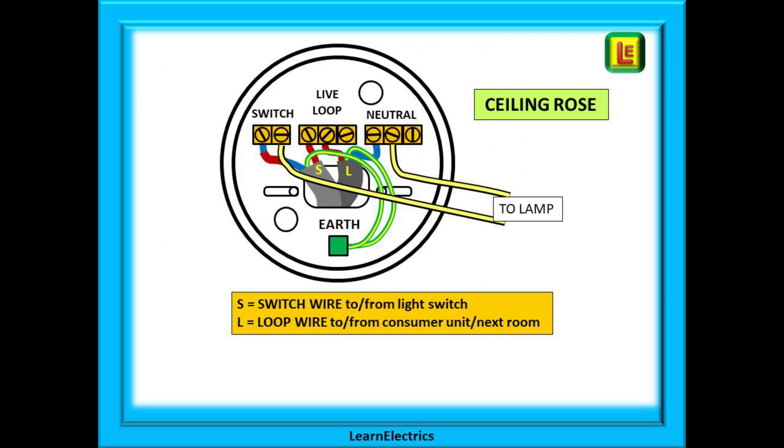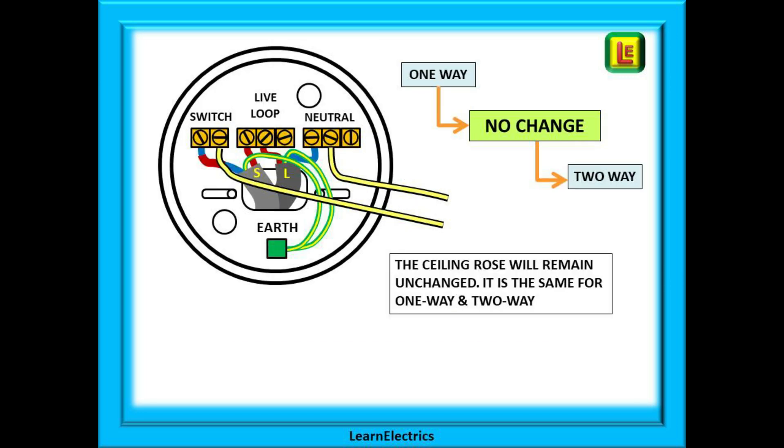We will use a standard three plate ceiling rose in this example and how to wire this up is fully detailed in the one-way lighting video. Marked S here is the switch wire to and from the light switch, and marked L is the loop feed from either the consumer unit or the previous ceiling rose. The ceiling rose will remain unchanged. It is the same configuration for one-way and two-way lighting. This means that if you change a one-way lighting circuit to two-way, there is nothing to do at the ceiling rose. It is all done at the switches.